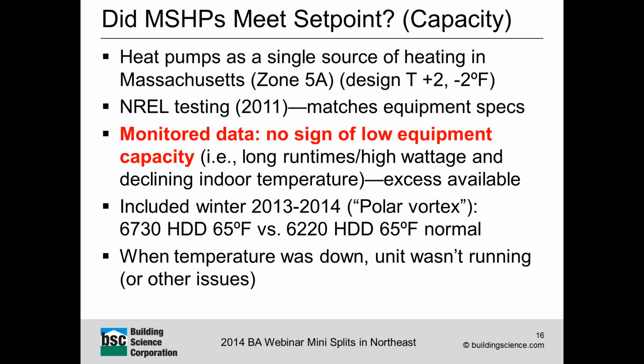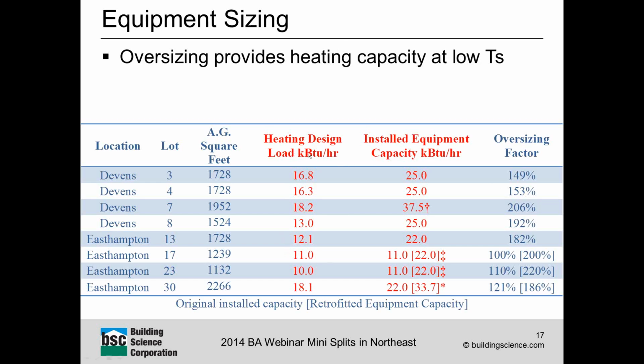That being said, one of the things you have to consider is the sizing of this equipment relative to the design load. So this table has the heating design loads for these various houses and the installed equipment capacity, and some of these are in brackets. Those are houses where typically one head was installed first, and then a second one was retrofitted afterwards down the road. I'll talk a bit more about that later. And this shows the oversizing factor. For most of these houses, we're in the 150 to 200% oversized range, and in these houses, after the retrofit, in the 200% oversized range.